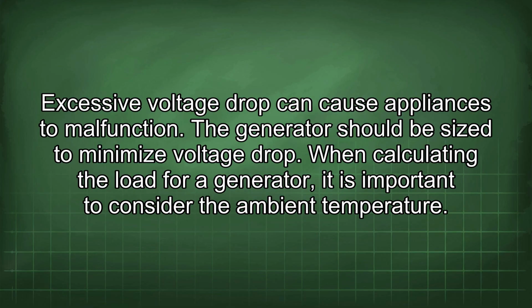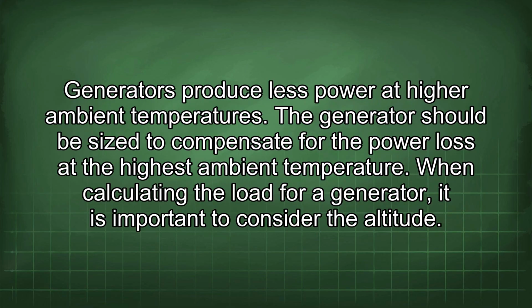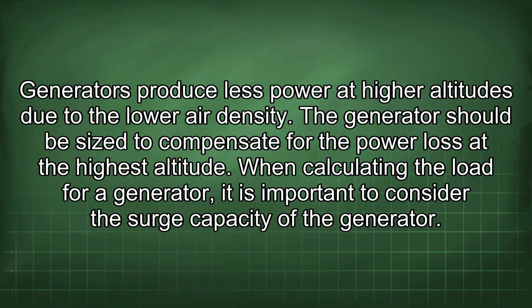When calculating the load for a generator, it is important to consider the ambient temperature. Generators produce less power at higher ambient temperatures. The generator should be sized to compensate for the power loss at the highest ambient temperature. It is also important to consider the altitude. Generators produce less power at higher altitudes due to the lower air density. The generator should be sized to compensate for the power loss at the highest altitude.